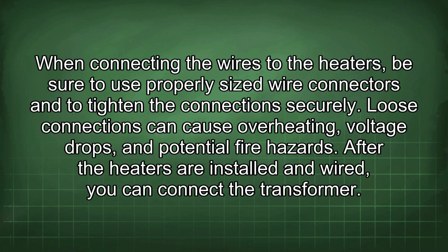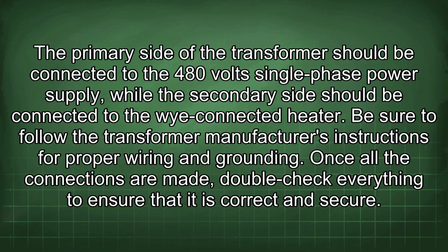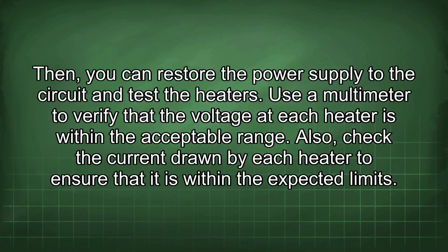After the heaters are installed and wired, you can connect the transformer. The primary side of the transformer should be connected to the 480 volt single-phase power supply, while the secondary side should be connected to the Y-connected heater. Be sure to follow the transformer manufacturer's instructions for proper wiring and grounding. Once all the connections are made, double-check everything to ensure that it is correct and secure. Then, you can restore the power supply to the circuit and test the heaters.